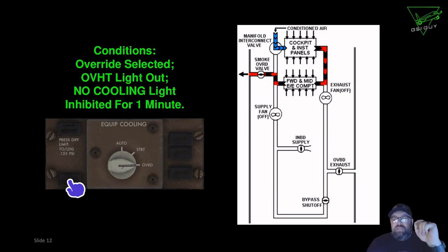And that's telling me that I'm at the end. I've gone to standby, didn't work. Gone to override, didn't work. So that's it. You're not cooling the airplane, and you're not cooling the equipment anymore. So in that particular case, that's where I think most QRHs are probably going to say land at the nearest suitable airport. And again, you've got about 90 minutes before you start losing essential equipment.